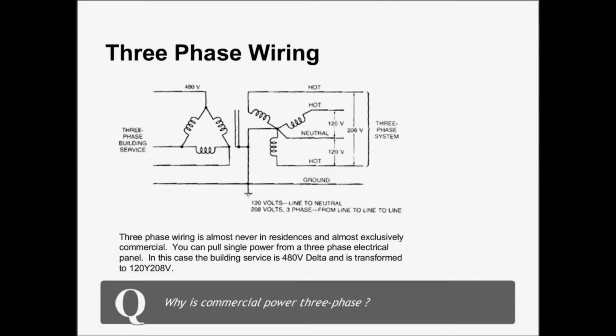So the next one I want to show you, and this is really more for just familiarity. This is three-phase wiring, and this is what you'll see in a lot of commercial buildings. Essentially, for example, in a data center, you'll see 480 volts coming into the building, and then they will use a transformer to step it down to 120, 208. And that's the most common voltage you see in data centers.